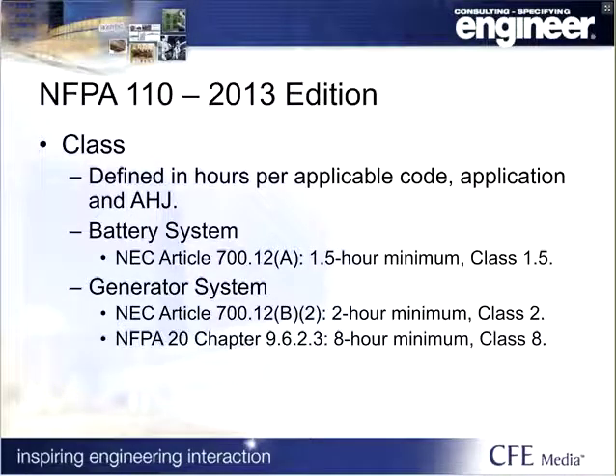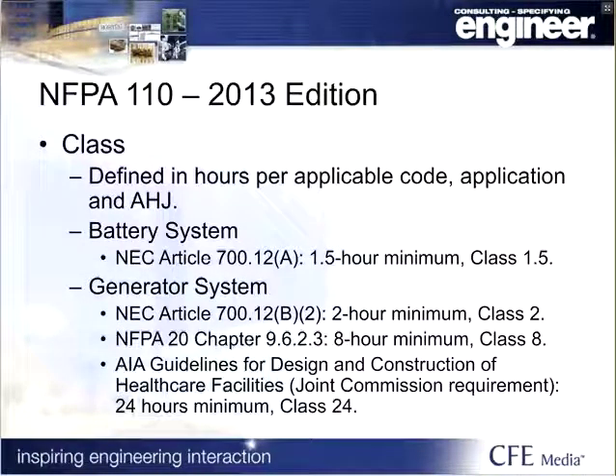NFPA 20, which addresses the installation requirements for fire pumps, calls for a minimum fuel supply for 8 hours of continuous runtime. And another example is inpatient healthcare facilities that are accredited through JCAHO, or the Joint Commission on Accreditation of Healthcare Organizations, need to have a minimum of 24-hour fuel supply per the AIA guideline for design of construction healthcare facilities. This could be more than 24 hours based on the jurisdiction, but the minimum in the guideline is 24.